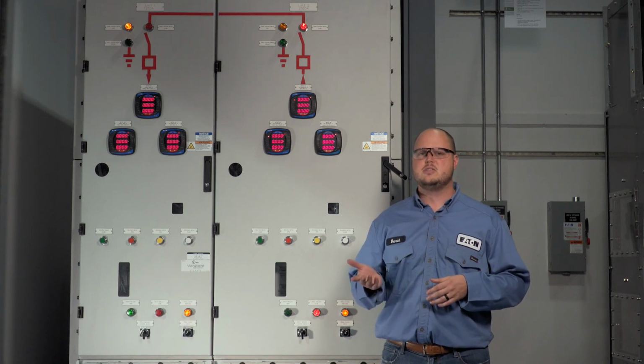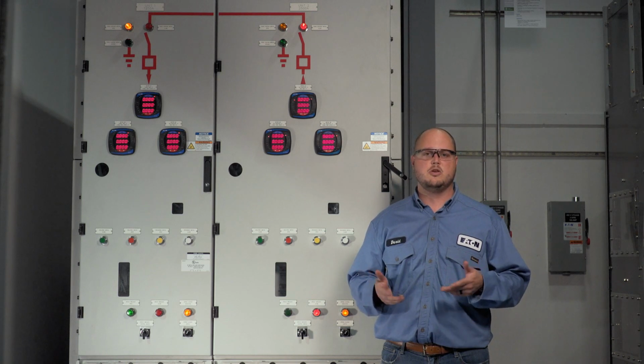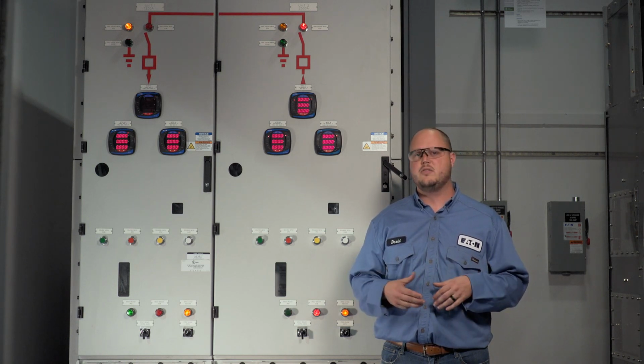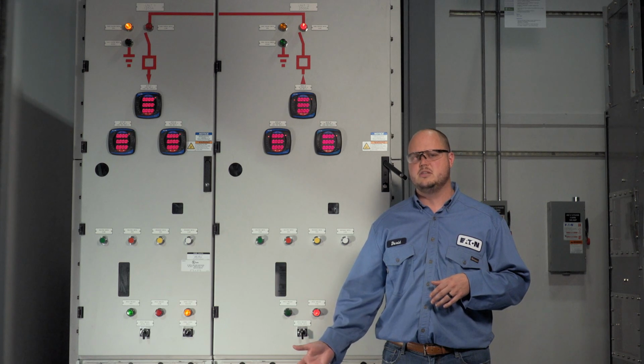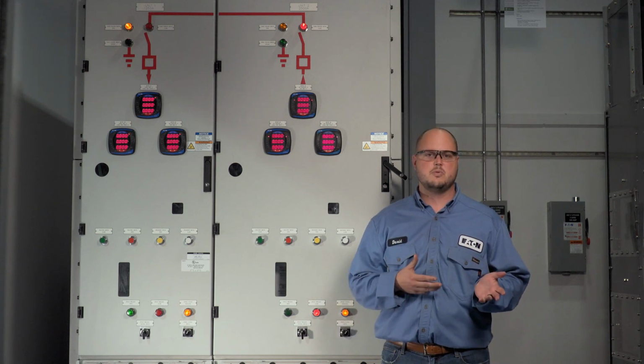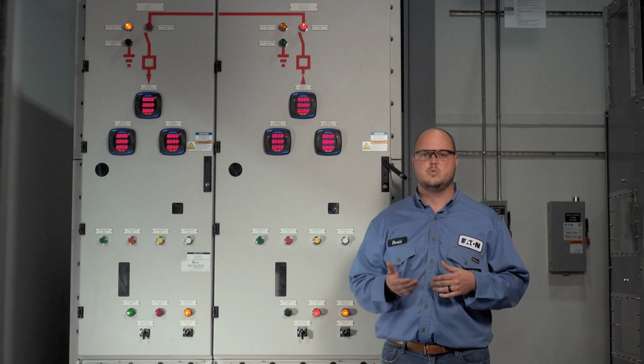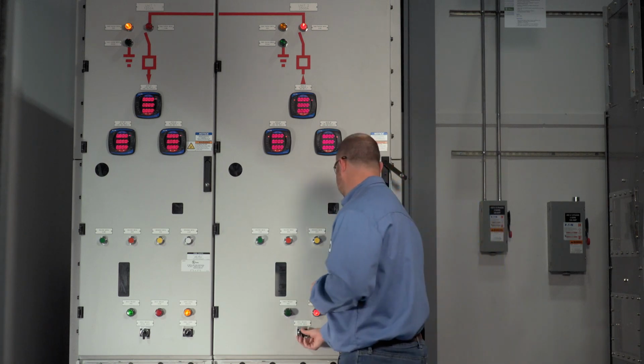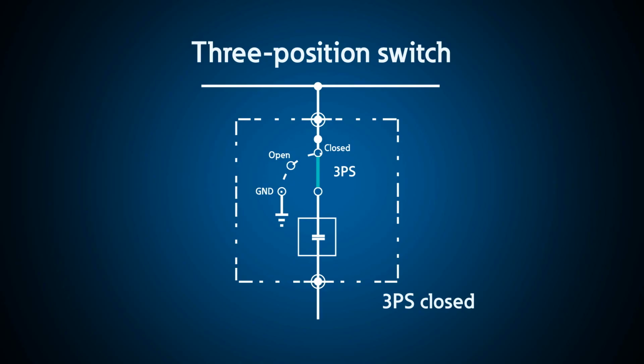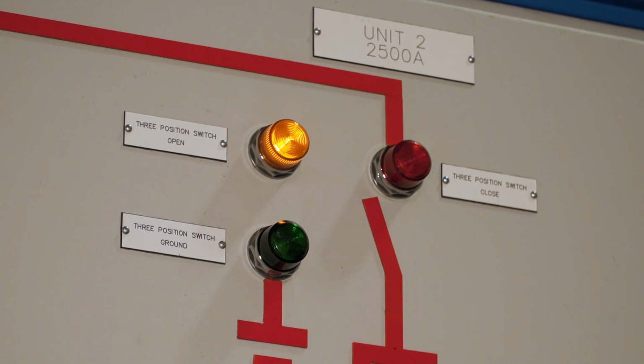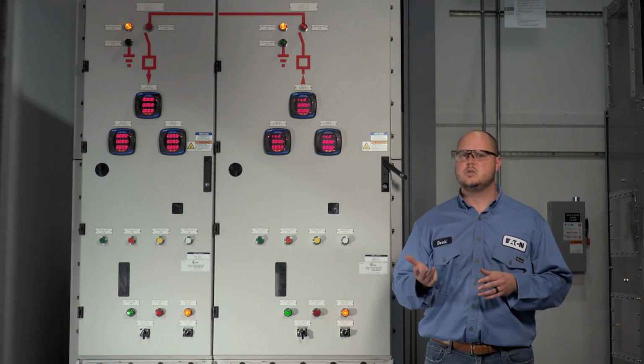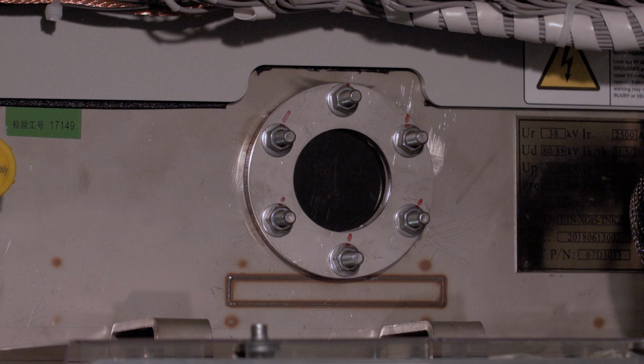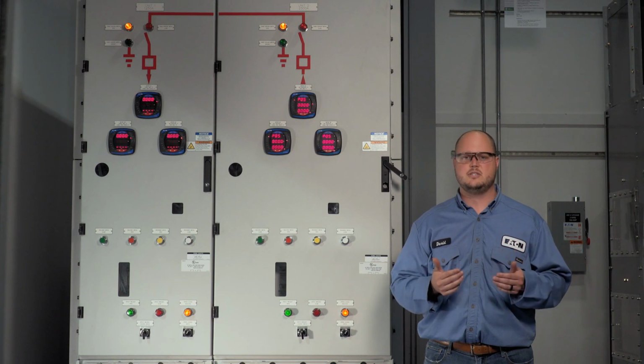The breaker and 3-position switch are currently closed as they would be under normal operating conditions. To ground the cables and lock the switch in a safe position, the operator first opens the circuit breaker and then isolates the 3-position switch. The operator would then use the 3-position switch camera or the viewing port on the front of the switchgear to visually verify that the 3-position switch is in the open position.